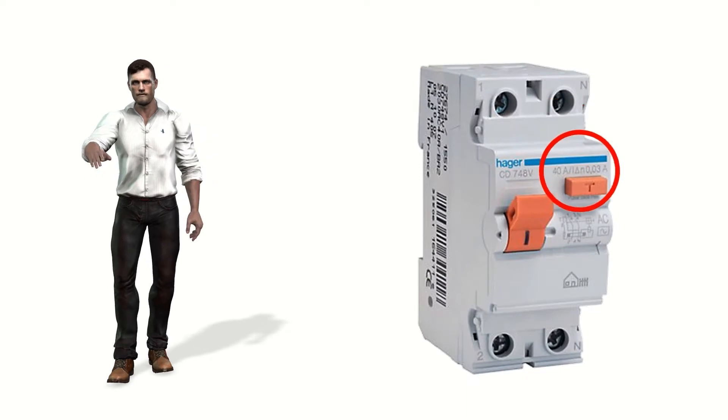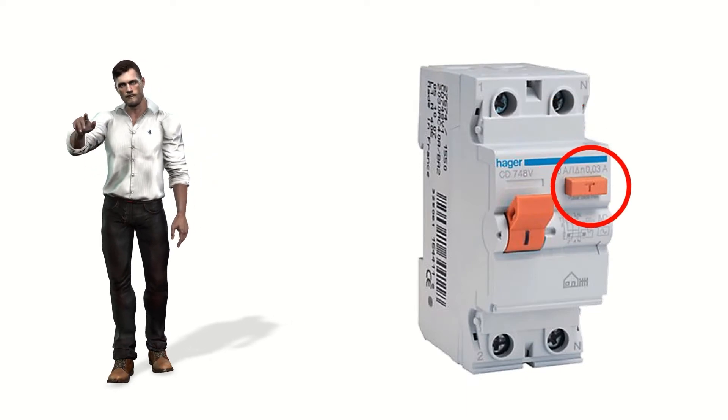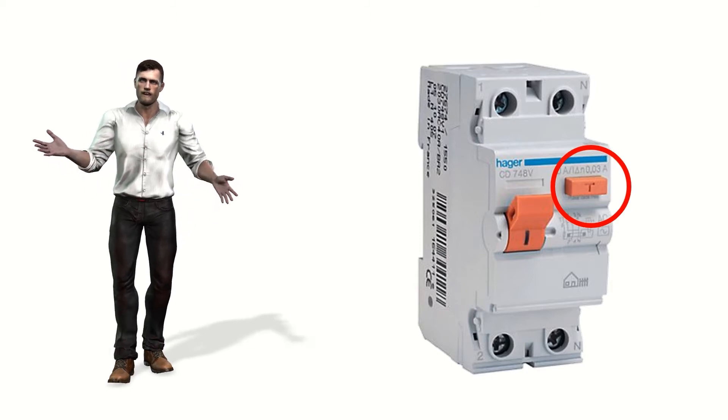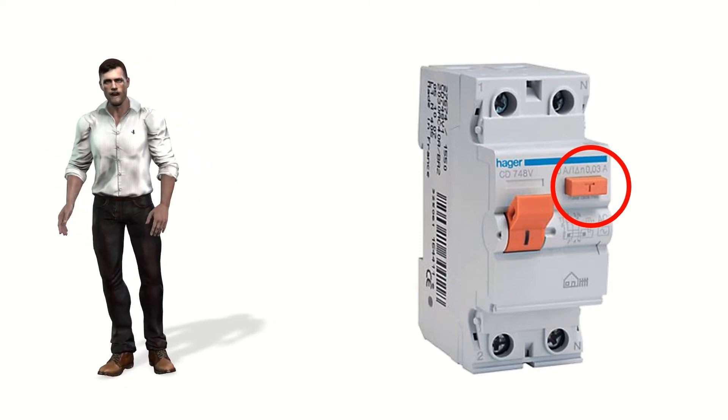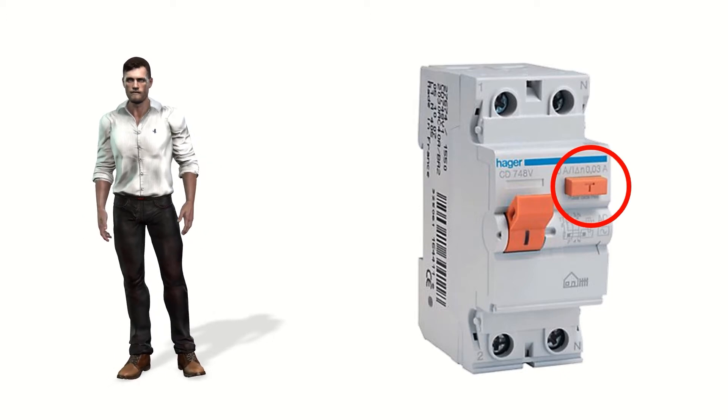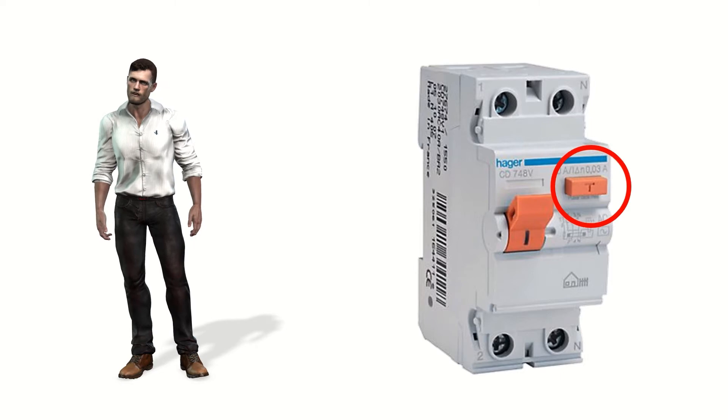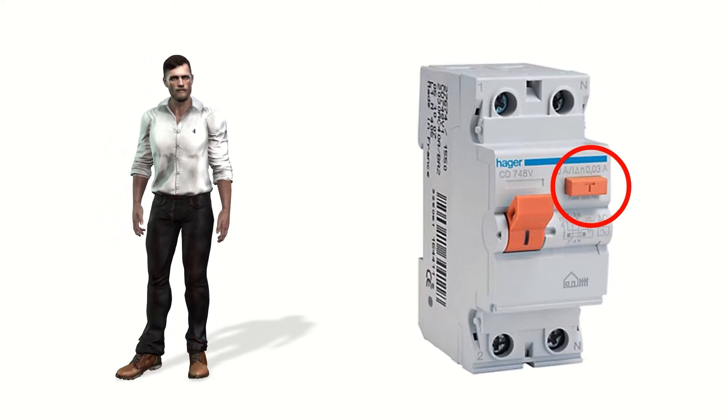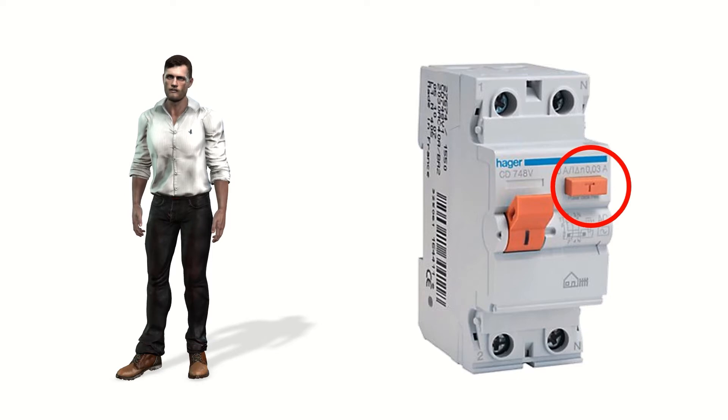As we see in the image, the differential protections or RCD usually incorporate a test button. This test button connects a resistance between phase and neutral outside the toroid, simulating a known leakage current, enough to activate the differential protection. Although this test is a help to know if the residual current device is capable of being activated, it is not enough to determine if that differential protection really works correctly.